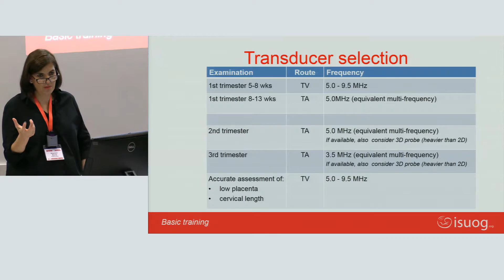better resolution. But these days you have something called multi-frequency probes, or the 3D probes. Now, multi-frequency probes have many frequencies in one transducer, and that means you have good resolution and penetration. And on your ultrasound machine, if you're scanning with a multi-frequency probe, you need to ask the technician where to change the frequency, because every ultrasound company calls it a different name. Some of them call it high definition, some of them call it frequency. Ask them, where do you change the frequency on that transabdominal probe if you've got a multi-frequency probe, so that you can set it higher or lower.